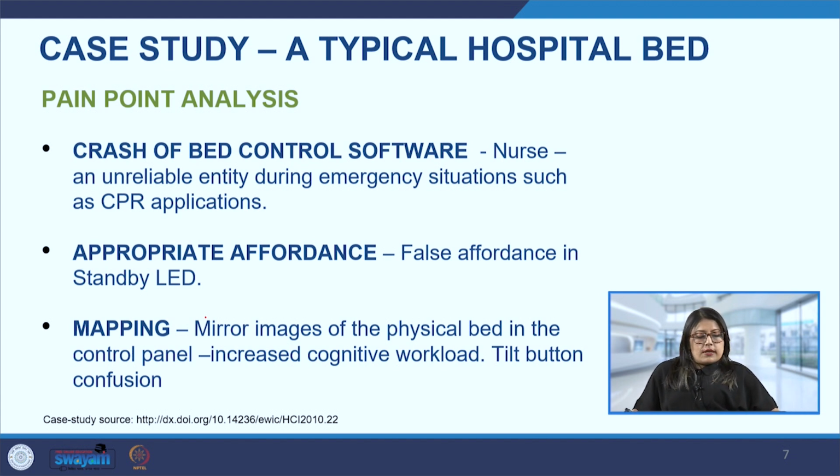So the first was the crash of the bed control software. During certain emergency situations where CPR is to be administered by the nurse to the patient, in those critical cases they found that the bed control software was crashing. That of course is a very dangerous situation, because in order to revive the patient, the nurse needs to carry out certain important functions, and if the bed is not supporting them, then of course it is a big failure.